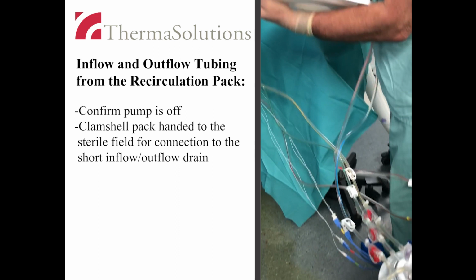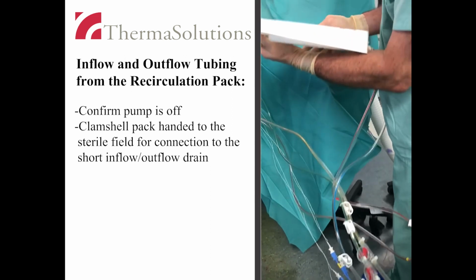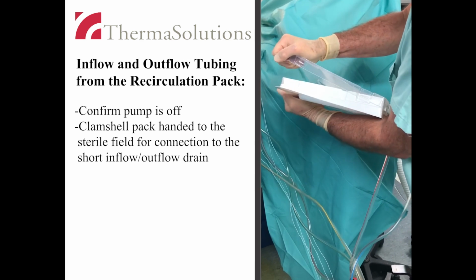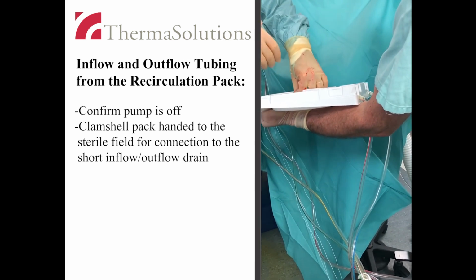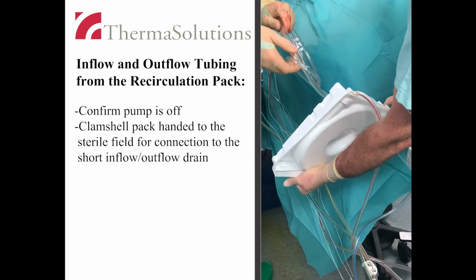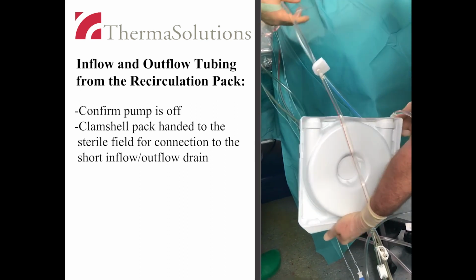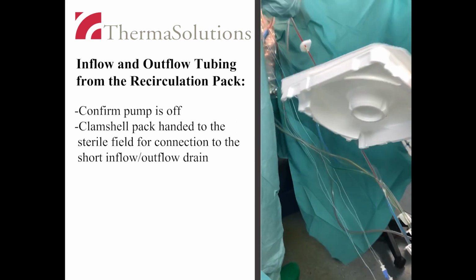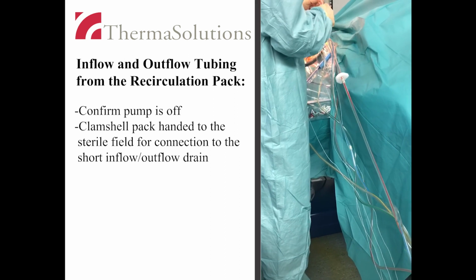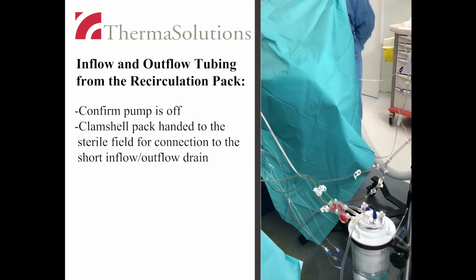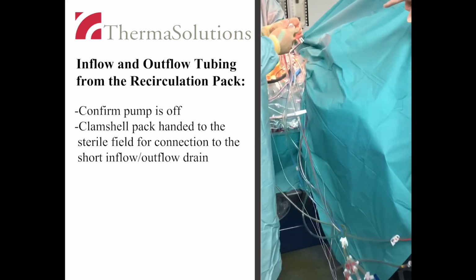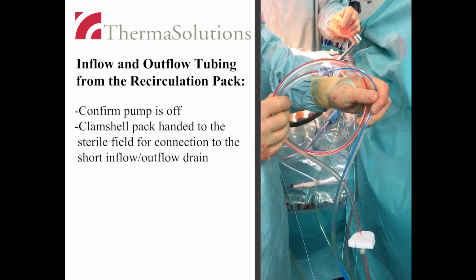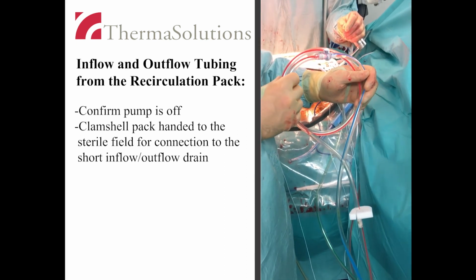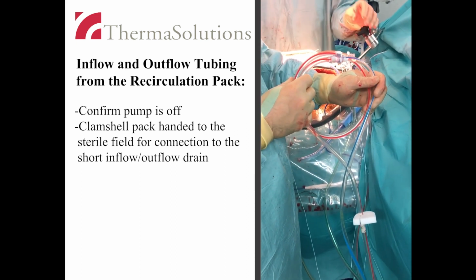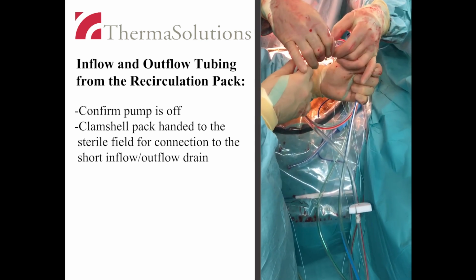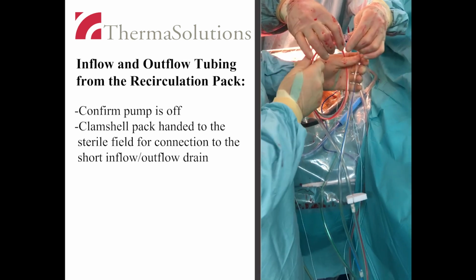The tubing going to and returning from the clamshell pack is clamped. The clamshell is opened and presented to the sterile field. OR staff in the sterile field removes the tubing coil for transfer into the surgical field. The sterile, non-sterile demarcation on the tubing is pre-marked with tape. Once on the surgical field, the coil is separated using the quick release fitting.